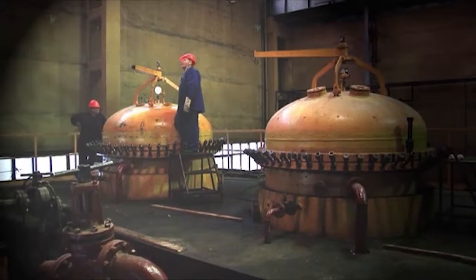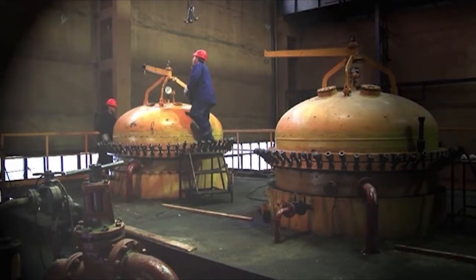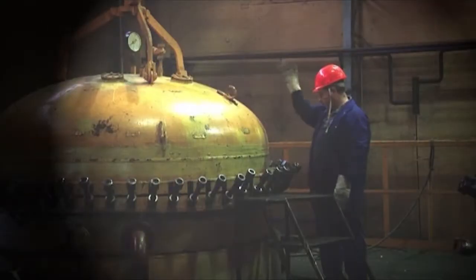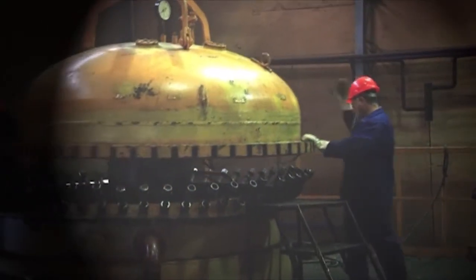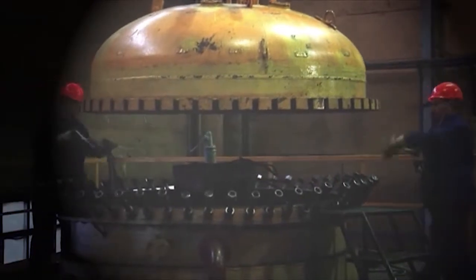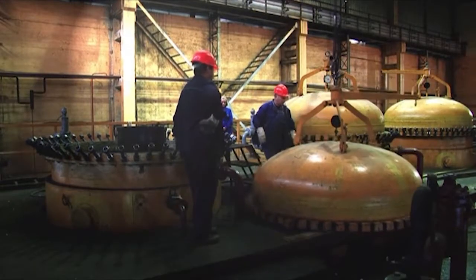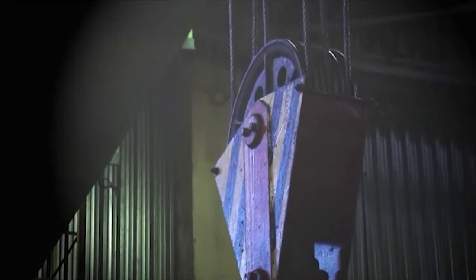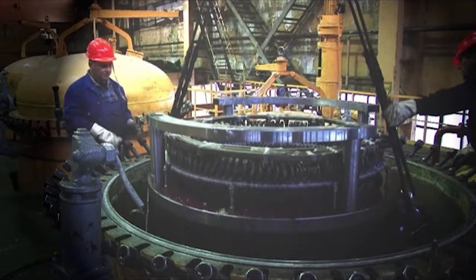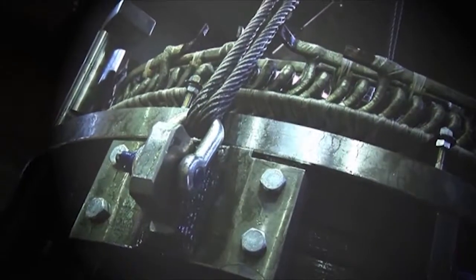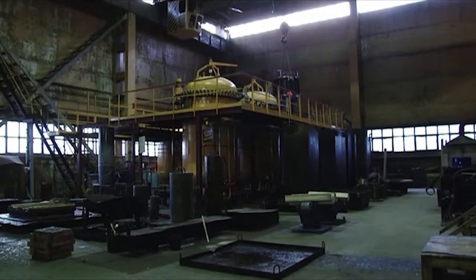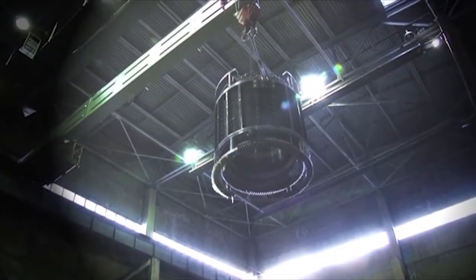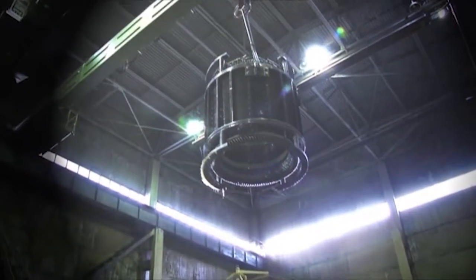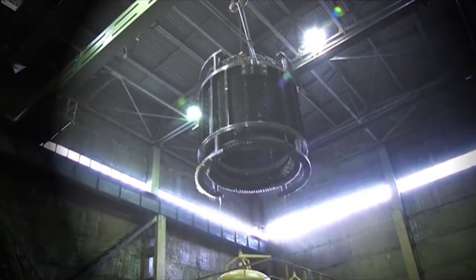St. Petersburg plant has many years of valuable experience in VPI, or the Monolith 2 system insulation of bar and coil windings with dry tapes, as well as in resin-rich insulating with impregnated tapes. The essence of the first method, called Monolith, is as follows. A stator with dry tape insulated coils, which have been installed into it, is put into the autoclave. The autoclave is evacuated so as to remove volatile substances and to provide for the high-quality insulation impregnation. Then a compound is fed from a mixing tank and held under pressure. After that, the stator is removed from the vessel and put into an oven to dry.